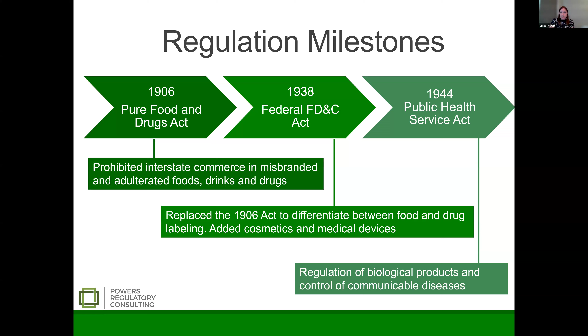The Public Health Service Act came along after that and added a lot of biological products and vaccine information. And then when we get into real medical devices, the first standalone amendment to that act was in 1976. That established the 3 different medical device classes based on risk and the different regulatory pathways they needed. That's the one we're still operating under, and it's the one that invented the 510K pathway as well as the PMA pathway.